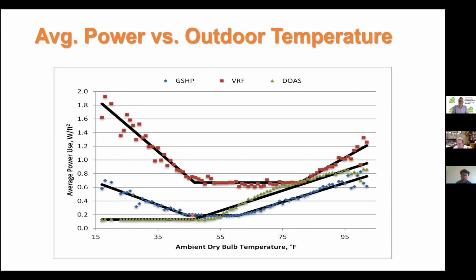And the actual minimum values vary between the ground source heat pump and the VRF system. But notice around, say, 50 to 55 degrees, the ground source heat pump system is using about 0.2 watts per square foot, and the VRF system is using about 3 times that. And in Atlanta, there are a lot of hours in this region. So that's one of the reasons why there's just so much difference in the performance.